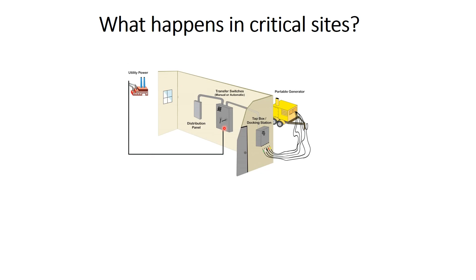So what happens here is that we now have two sources of power. We have the utility power and we have the generator power. This is a backup generator or a standby generator. So we have here something which is called a transfer switch, sometimes called the ATS or automatic transfer switch, or a manual transfer switch. So what does this do? During normal conditions, we have a distribution panel here. This one provides power to our site, as an example, a hospital. This distribution panel takes electrical power from the transfer switch.